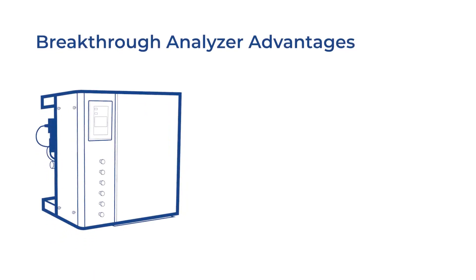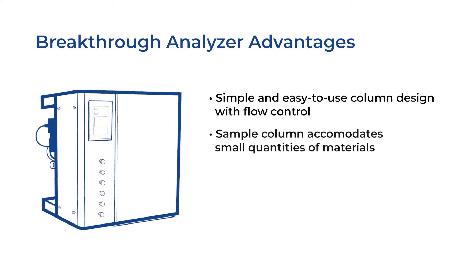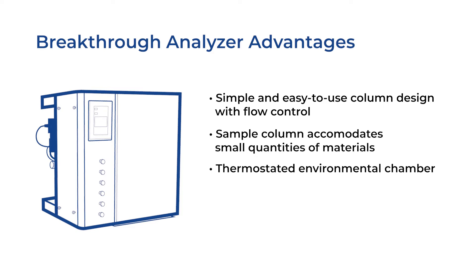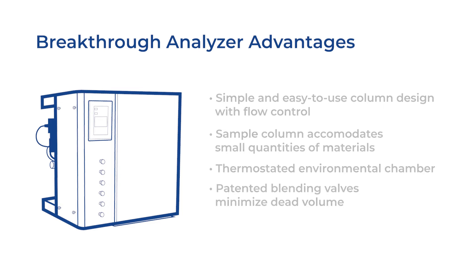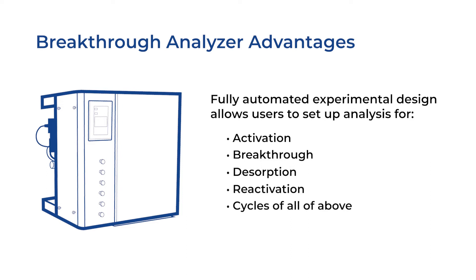This is especially important if your application involves the separation of hexanes or xylenes. The BTA offers several advantages. It has a simple column design with exceptional flow control, which enables multiple gases to be used with highly controlled blending. The sample column accommodates small quantities of material, which is ideal for R&D applications. A thermostated environmental chamber provides constant temperatures and prevents condensation of vapor streams. The patented blending valves provide advantages for gas mixing and minimization of system dead volume. The fully automated experimental design allows users to set up analyses for activation, breakthrough, desorption, and reactivation, as well as cycles of all of the above.